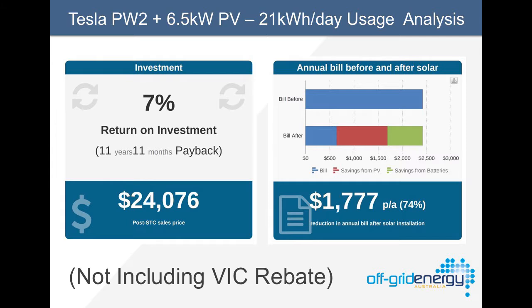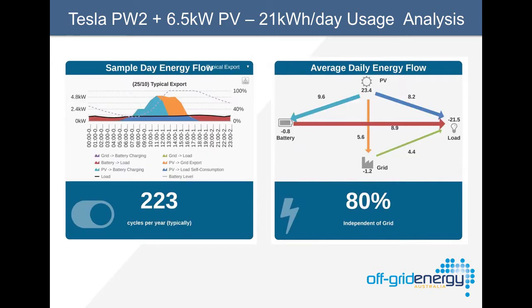If you go to the next page, there's some more information on what this looks like. Might be a little bit hard to see all those numbers, but one that I think is important is 223 cycles per year. What this program does is overlay the solar production for that area over the consumption data, and it gives us a scenario of what would have happened over the last 12 months if we had that battery in. So that Tesla battery is being cycled maybe 2 out of 3 days completely - you could say there's a case to put more solar on if you want to utilise that battery more.